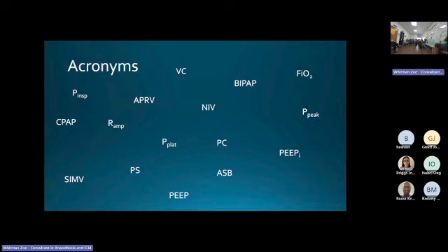I meant to go and look at the ventilator because I can't remember what ramp is called on the new one. I forgot. Ramp is the speed of going from expiratory pressure to inspiratory pressure. It's set at 0.2 seconds as a default on our ventilators.